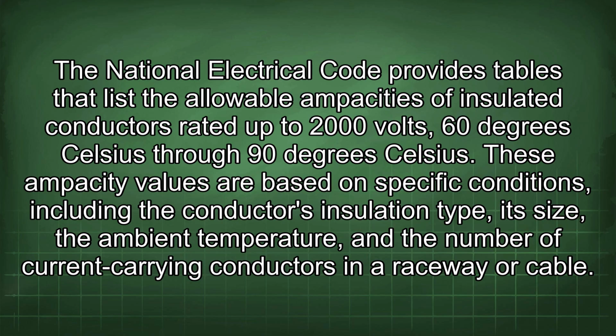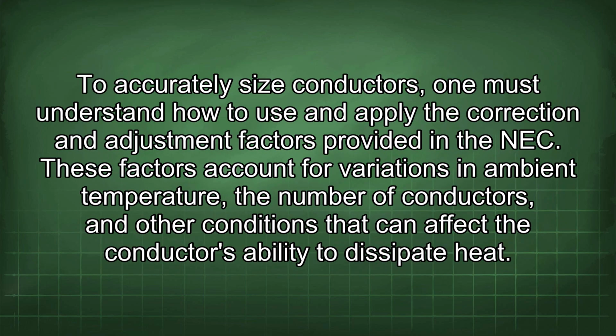The National Electrical Code provides tables that list the allowable ampacities of insulated conductors rated up to 2000 volts, 60 degrees Celsius through 90 degrees Celsius. These ampacity values are based on specific conditions, including the conductor's insulation type, its size, the ambient temperature, and the number of current carrying conductors in a raceway or cable. To accurately size conductors, one must understand how to use and apply the correction and adjustment factors provided in the NEC. These factors account for variations in ambient temperature, the number of conductors, and other conditions that can affect the conductor's ability to dissipate heat.